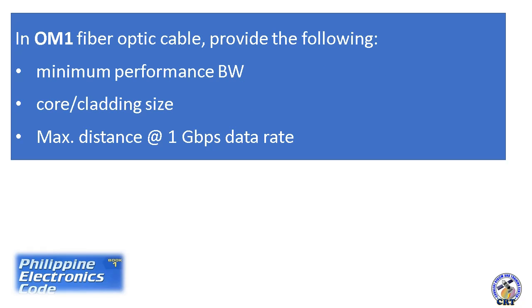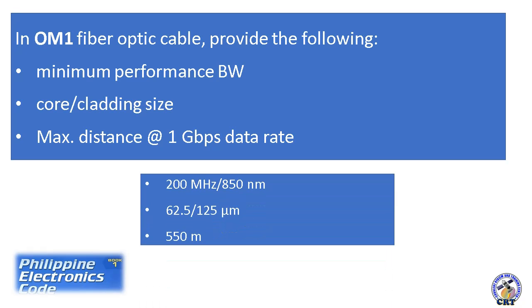In OM1, fiber optic cable provides the following. By the way, when we say OM, it is optical fiber multimode. So, it provides the following: minimum performance bandwidth, core cladding size, and the maximum distance at 1 Gbps data rate. For the minimum performance bandwidth, it is 200 megahertz with wavelength 850 nanometer. For the core cladding size, it is 62.5/125 micrometer. And for the maximum distance, it is 550 meters.